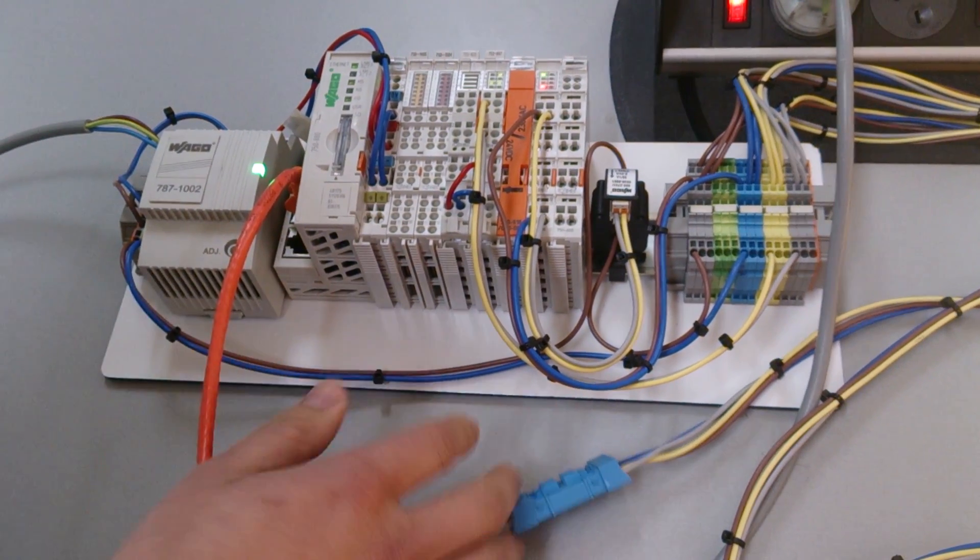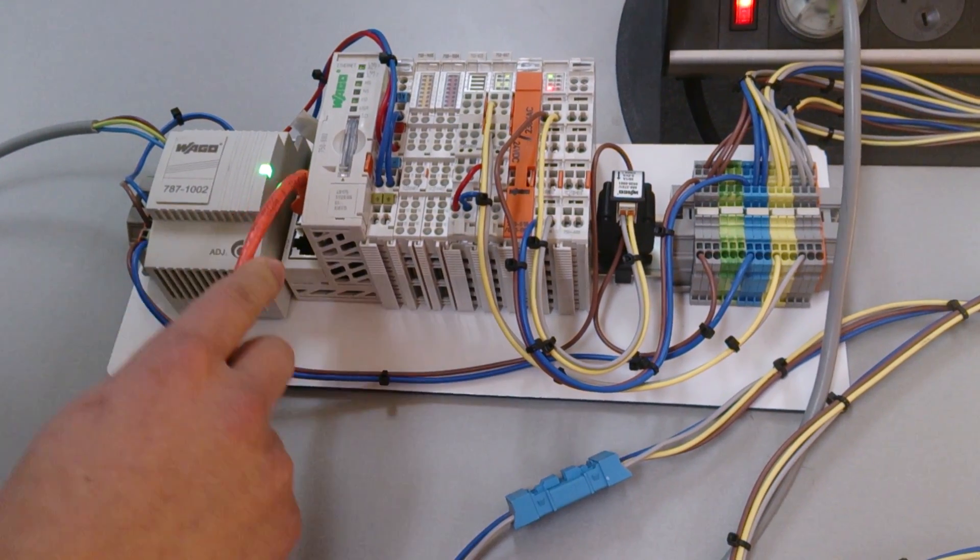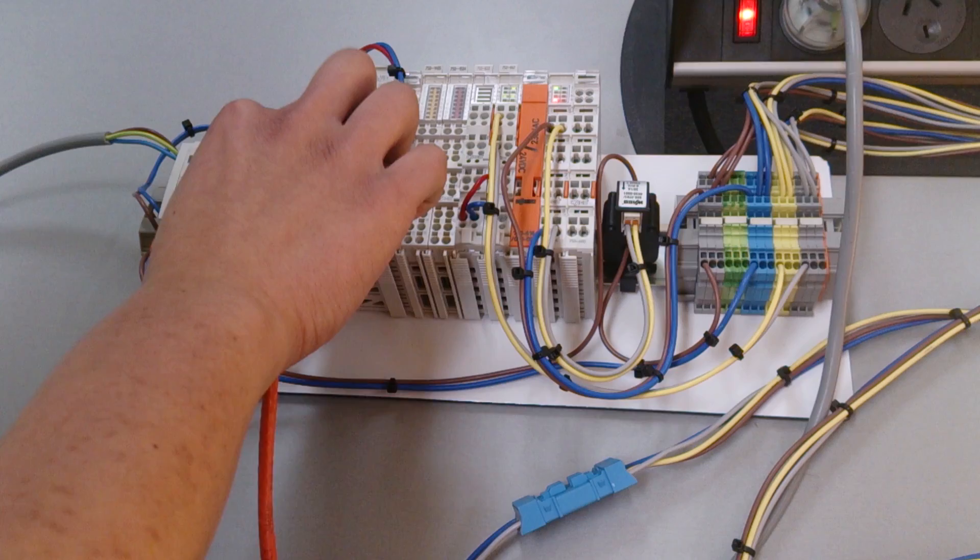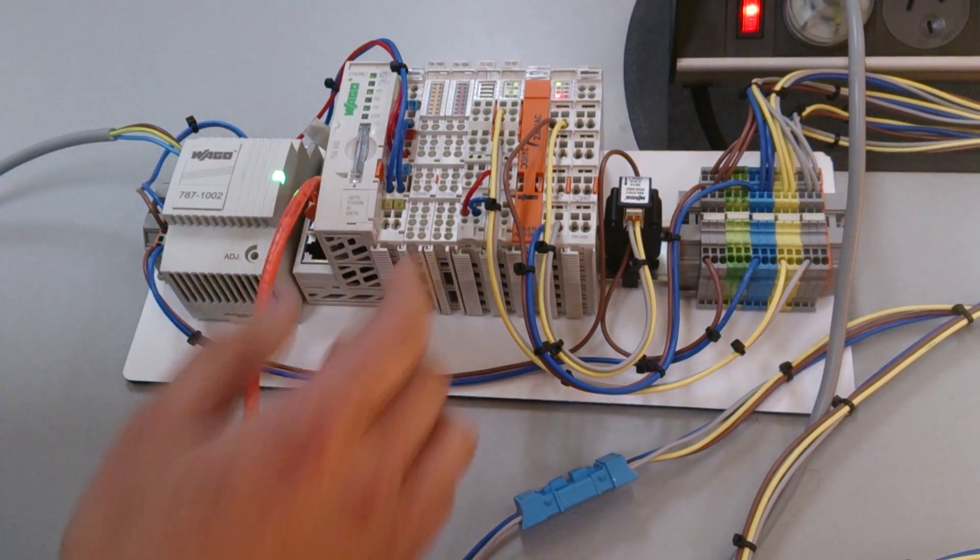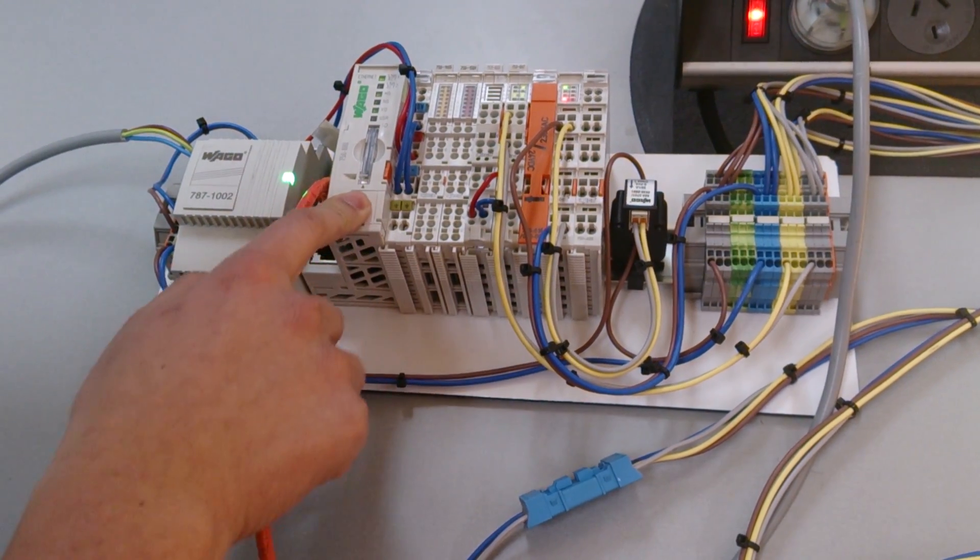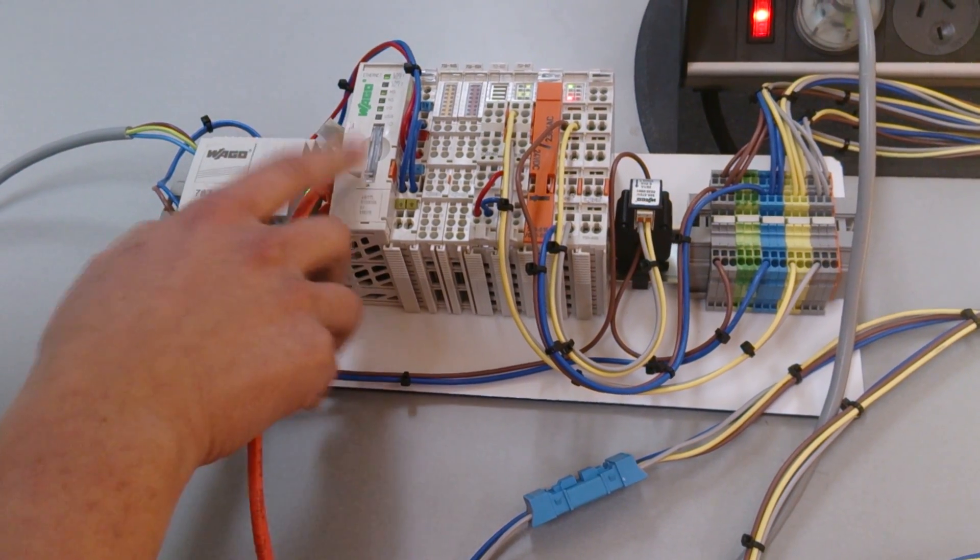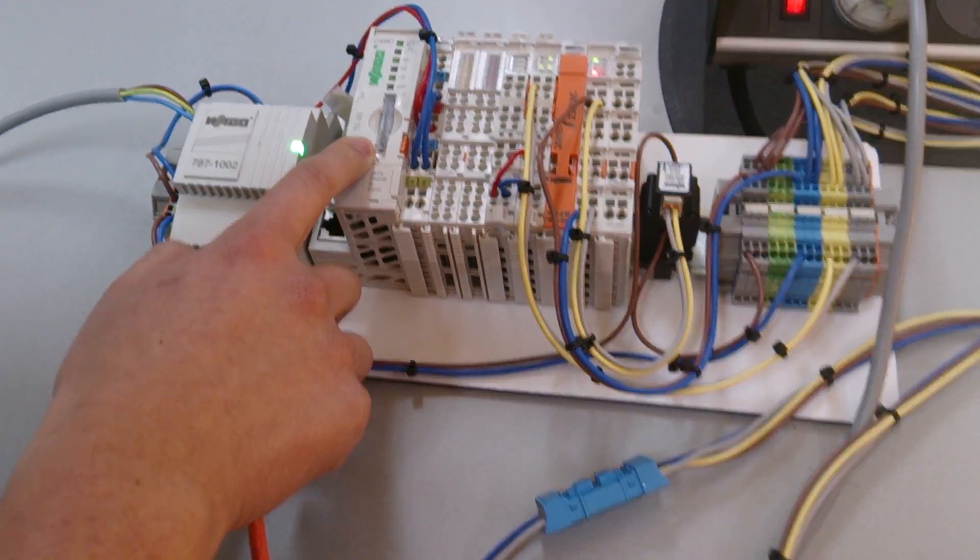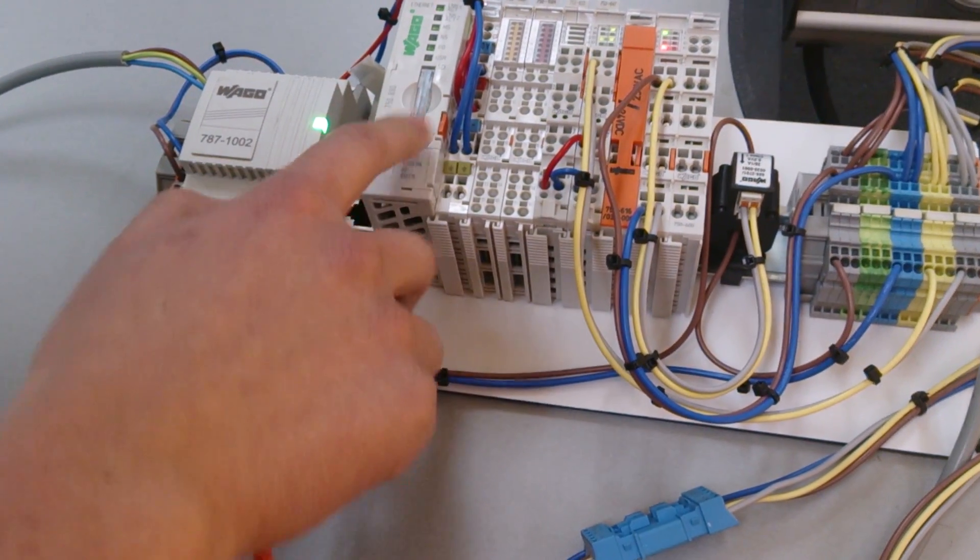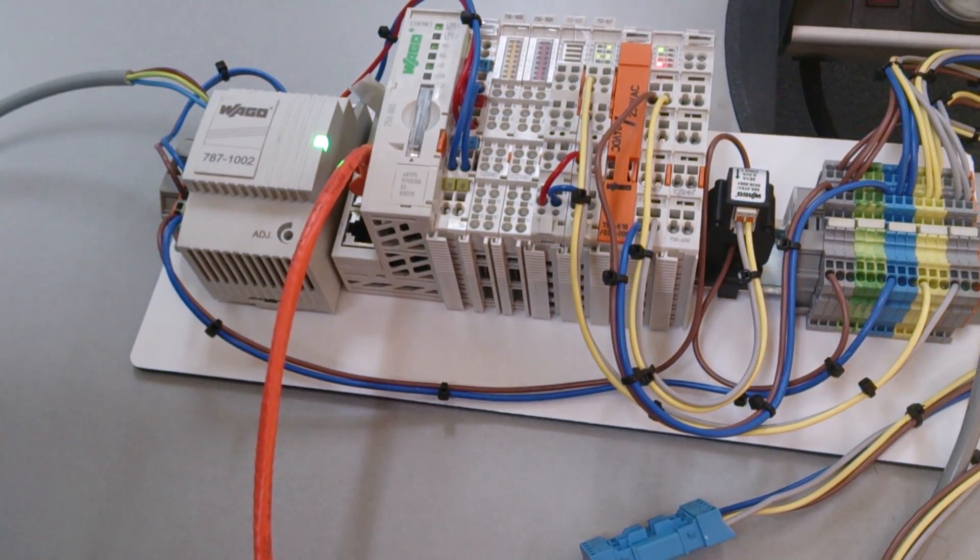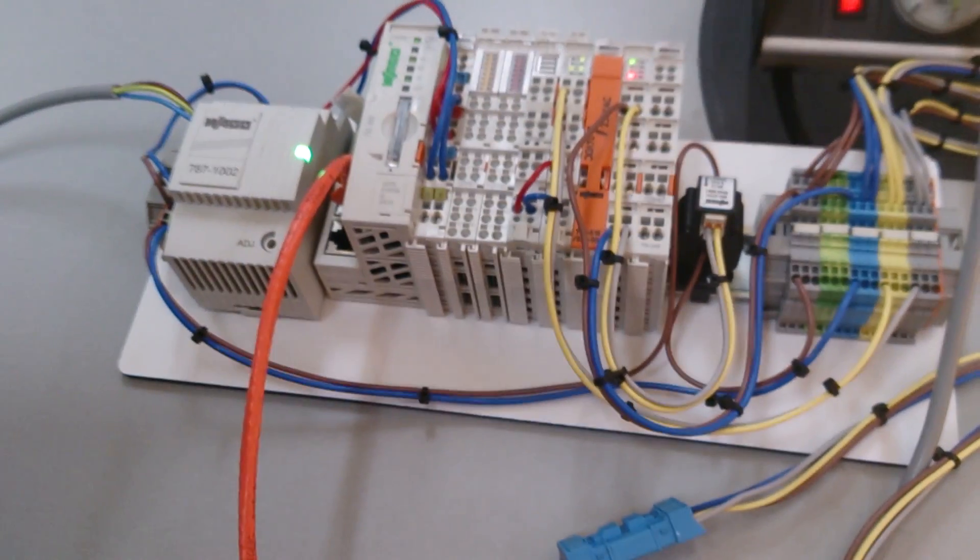Alright, so here we have automation set up for DALI lighting. You can see here that this is the 750-880. It comes with an SD card slot so you can use that for power monitoring and data logging.